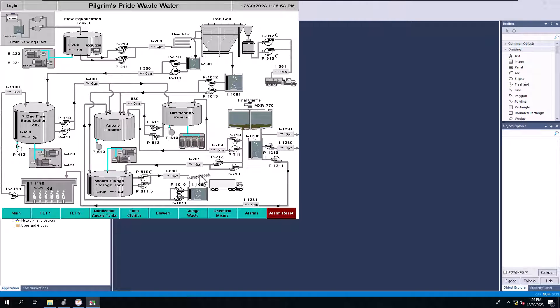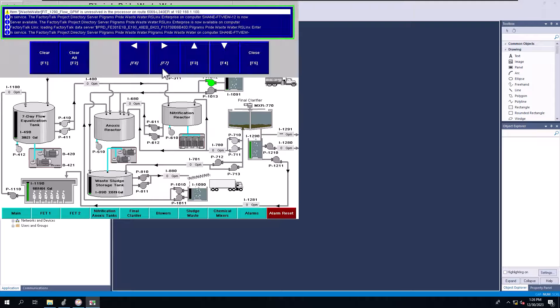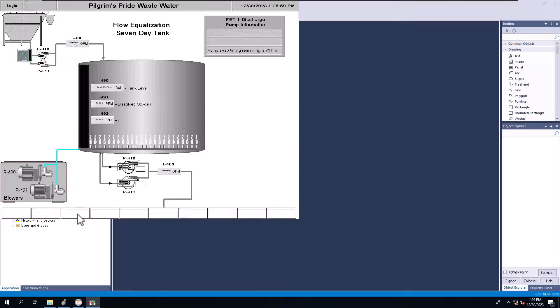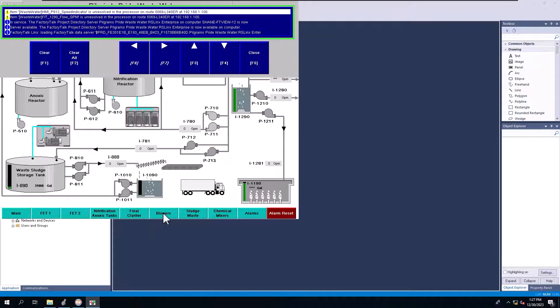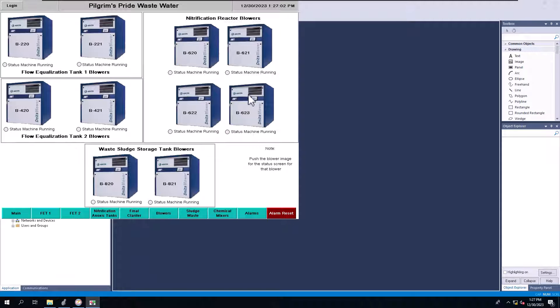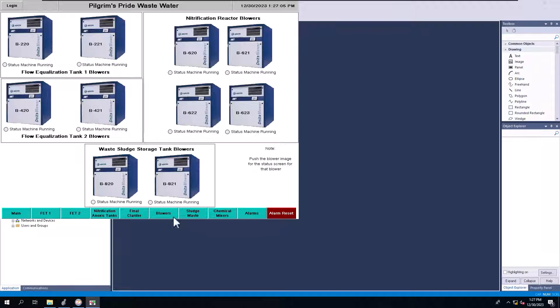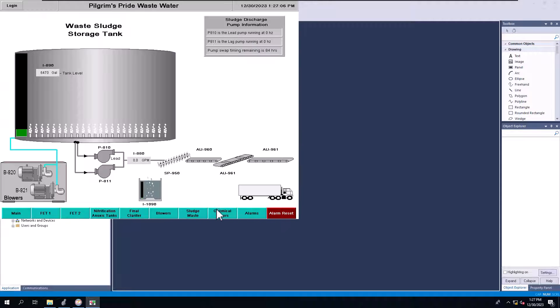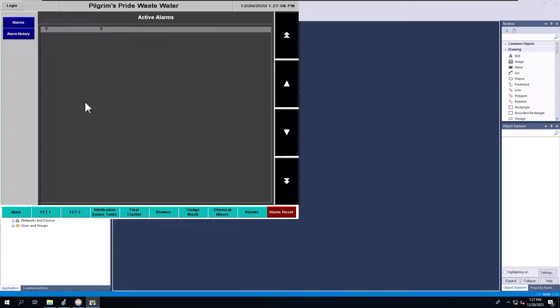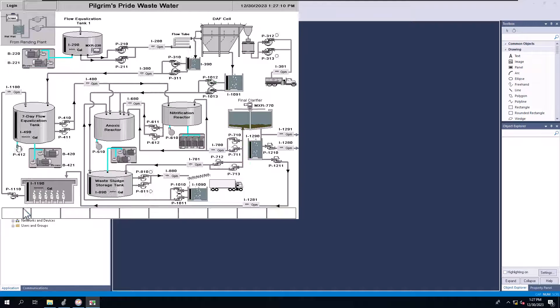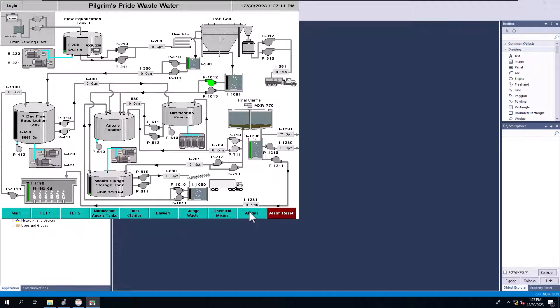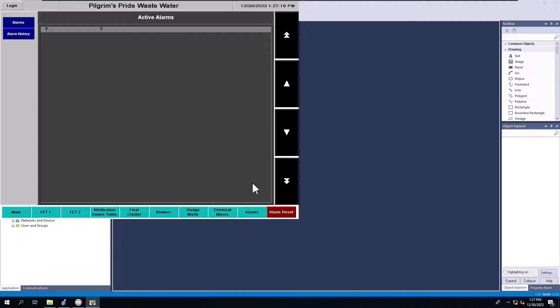I'm not showing my panel view just because the simple fact of it's going to be the same thing that I'm showing you here. It populates right here. You can easily see everything is working. You can see, I do have all of my things working. You can tell right here, alarms, alarm history. I don't have any alarm history. Keep in mind on machine edition, your alarm history is based upon the last time the power got cycled or the last time you downloaded to it.